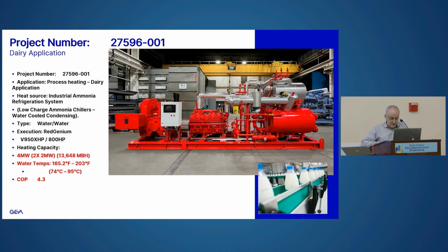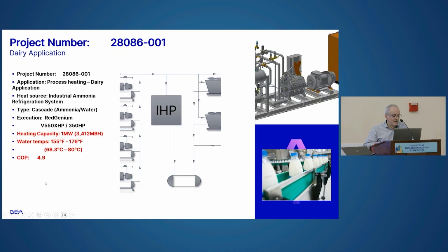It's 2 sets of 2 megawatts, 4 megawatts in total, making 95C water, with a COP of 4.3. The next 2 are going to be delivered by May. This one is going to a dairy plant in Idaho. It's a 1 megawatt heat pump. It's going to make about 80C water, 176F, for a COP of 4.9.